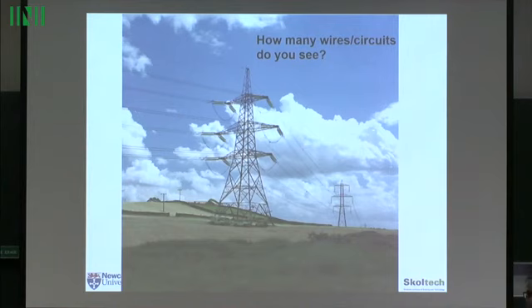This is a high voltage transmission line, probably 400 kV. It means that when the air is damp, you'll have discharges - it's called the corona effect. If it's a small wire, the voltage is very high across it, around that wire. So if you put two wires, you effectively make the cross-sectional area of the conductor much bigger, so the electric stress will be less. These are called bundled conductors.